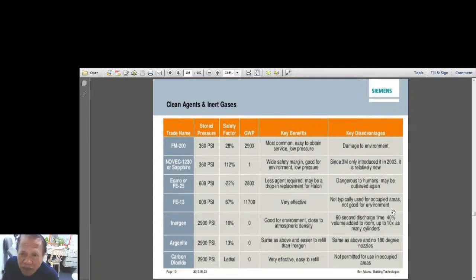So what is then the best? Let us review again. FM200, damage the environment. Novec, fairly new, but it seems there's no negative. ECARO, dangerous to humans. FE13, same. Inergen, 60-second discharge time, 40% more volume added, up to 10 times, so it's very big. So same as above. Oh my God. So it seems like Novec, although it is fairly new, is the one with no negative remarks by Siemens.